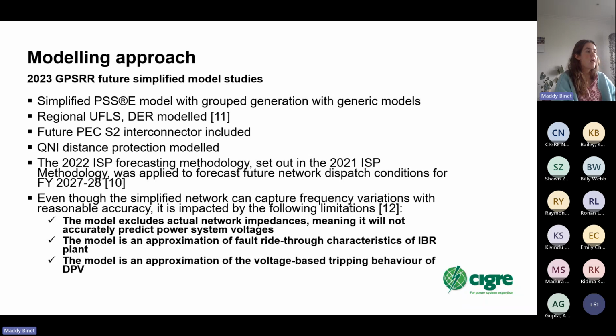But because, as it says on this slide, the simplified model can't accurately capture severe voltage disturbances, we only applied shallow faults in the simplified model. So it's not necessarily able to capture voltage-related load shake-off, as we're not able to do that in the simplified model anyway. And in the NEM, which is a bit different to the WEM, the frequency-dependent load relief is quite small—I think it's less than 0.5%.